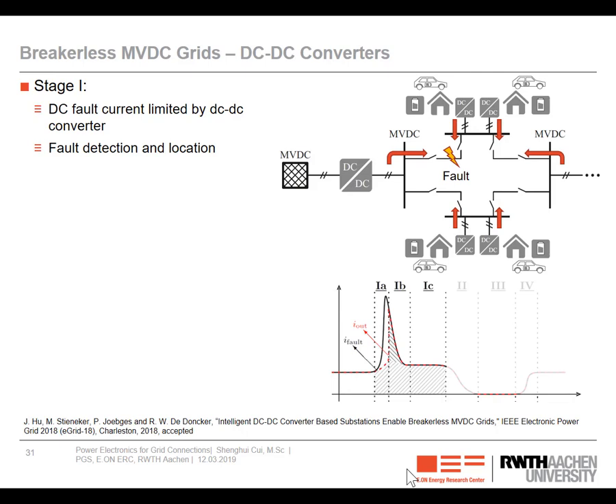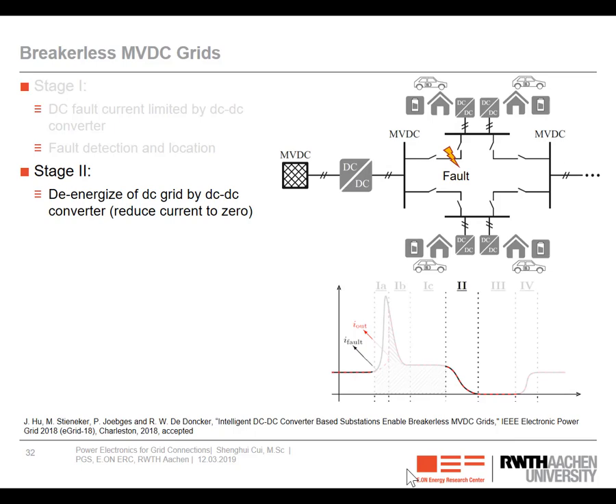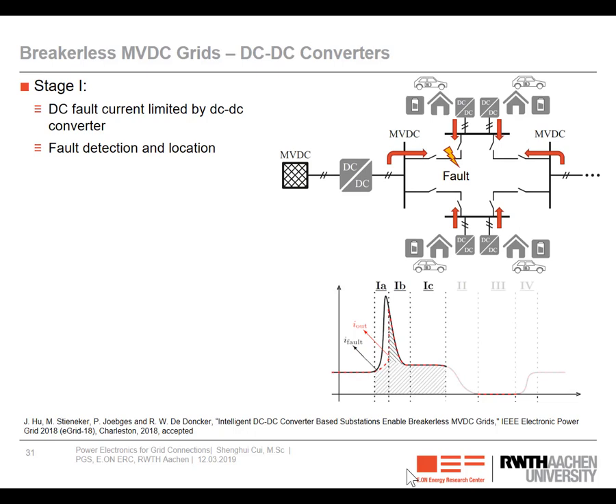As I mentioned before, in the first stage, when the fault occurs, then within several microseconds the fault current is built up, and when the DC link capacitor is fully discharged, the DC link current of the devices immediately becomes identical to the fault current. It is very high. Then we need to decrease the currents by the converter in an active manner. So here, this is the de-energization of the DC grid. So at first, we need to decrease the current to an acceptable level.